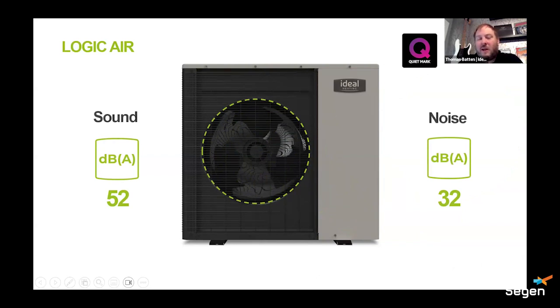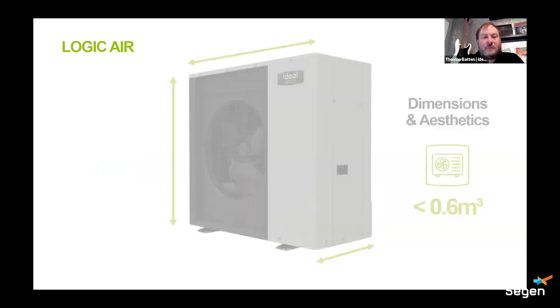So typically with a heat pump, what you find is you either need a giant evaporator and a slow running fan to get good efficiencies, or you have a small evaporator and a fan pulling loads of air through, which normally equates to that being really noisy. You can't really see it on here, but we've got a pretty funky fan design that's designed to pull more air through while running at lower speeds, and the evaporator wraps around the whole side of the heat pump. So we do get really, really quiet performance, but while still maintaining good efficiencies.